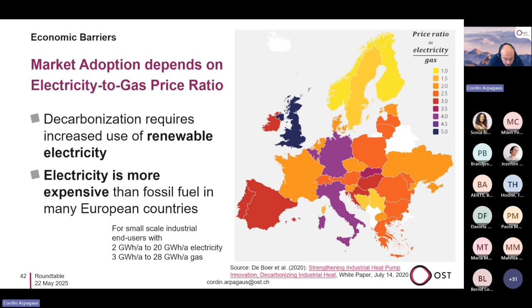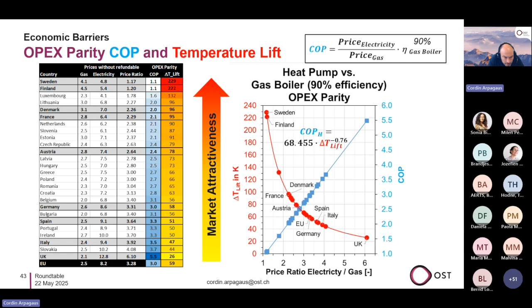We can have another view and translate this price ratio to application. What does it mean if the price ratio is lower? Then we have an economic COP that can be lower as well, and in principle we have a higher temperature lift that is still economical. When we have a higher temperature lift, we have more applications with potential for heat pumps - some applications have quite high temperature lifts from heat source to heat sink, and the COP of the heat pump will be lower than in other situations. But if the price ratio is also in a meaningful range, then these applications also have potential for heat pumps.